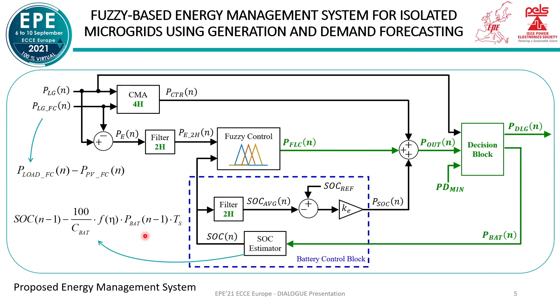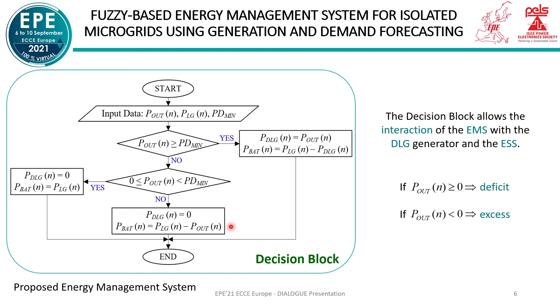If Pout is positive, the microgrid is presenting a power deficit. Therefore, the diesel generator should start whenever the technical minimum is exceeded. Otherwise, the battery must deliver the remaining demand power. Conversely, if Pout is negative, the microgrid presents a surplus power that will be stored in the energy storage system.